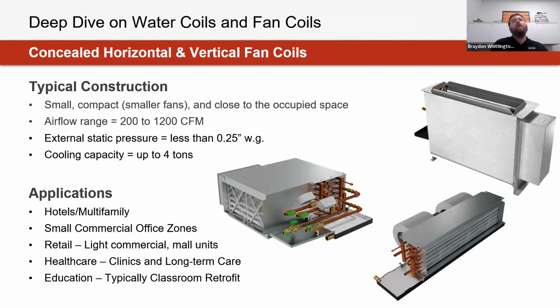These are concealed horizontal fan coil units, essentially a commodity style unit dealing with single zone applications. Commonly you might see this if you're traveling on the road within a hotel room, very common to see one of these installed by the window wall or right above the bulkhead, also in smaller office spaces. But essentially with these products, they deal with lower static, less than 1/4 inch, as well as lower airflows, so up to around 1200 CFM is where they're going to be the most effective.